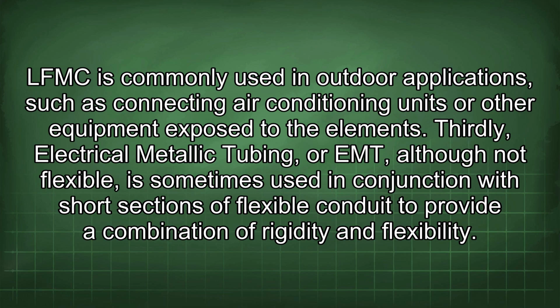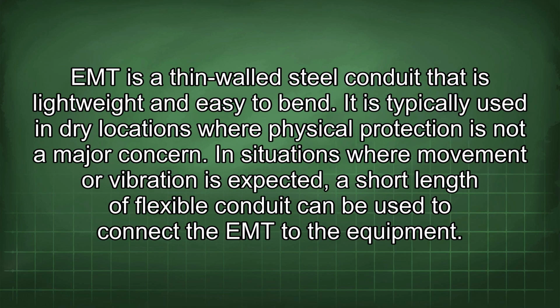Thirdly, electrical metallic tubing, or EMT, although not flexible, is sometimes used in conjunction with short sections of flexible conduit to provide a combination of rigidity and flexibility. EMT is a thin-walled steel conduit that is lightweight and easy to bend. It is typically used in dry locations where physical protection is not a major concern. In situations where movement or vibration is expected, a short length of flexible conduit can be used to connect the EMT to the equipment.